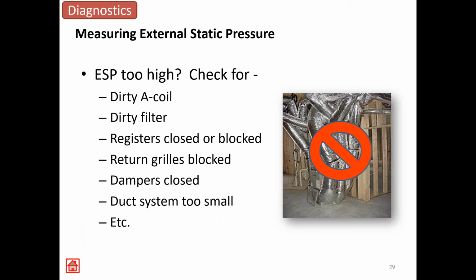Here's a great example of what not to do. External static pressure too high. You know, we've got dirty coils, dirty filters, registers blocked or closed, return grills that are blocked, and dampers that are closed for zoning type systems. This is a great looking job here. I know this would pass probably about anywhere, right?